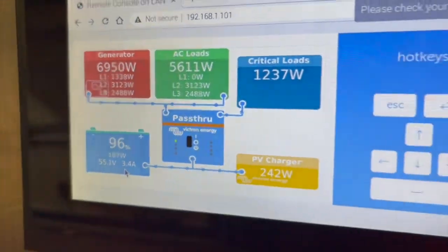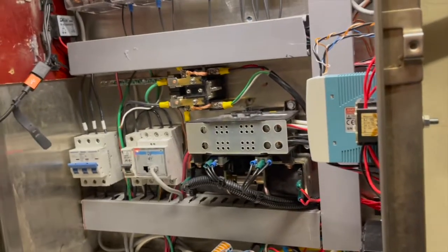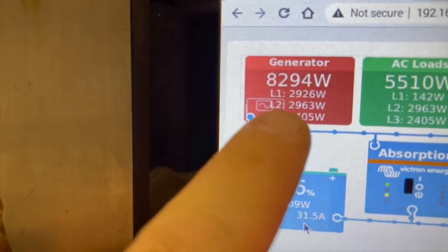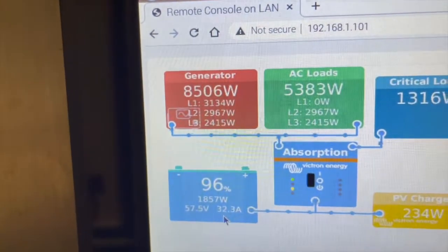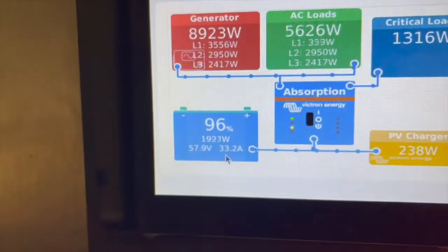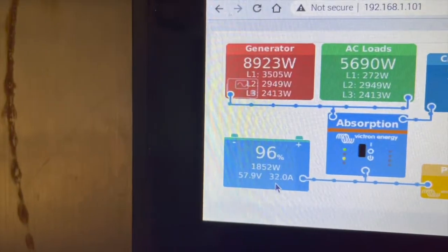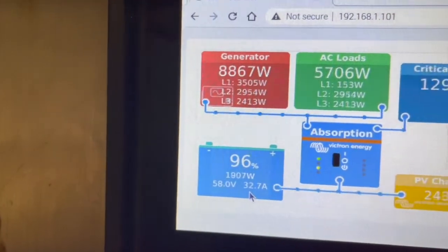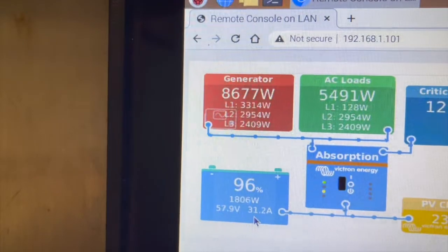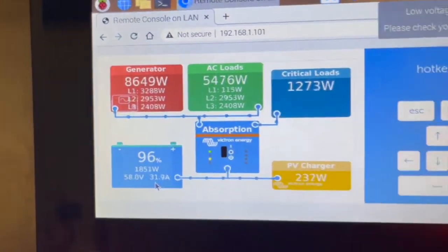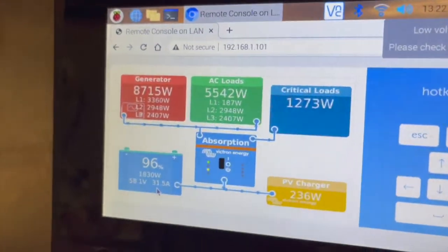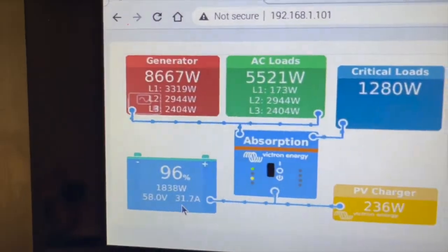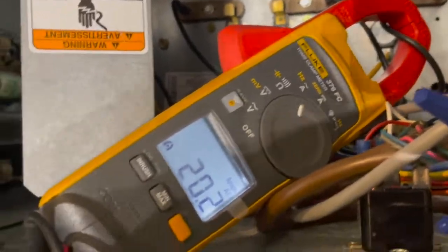There we go. So now that I have kicked on the heater for the house, I have enabled that 1 heating element. As you realize, leg 2 and leg 3 have just jumped up to almost 3,000 watts each. Pulling about 8 kW from the generator. So each leg is only able to pull a maximum of 5,000 watts. Overload it a little bit higher, but it seems to handle it. There you go. So that one heating element is pulling 20 amps.